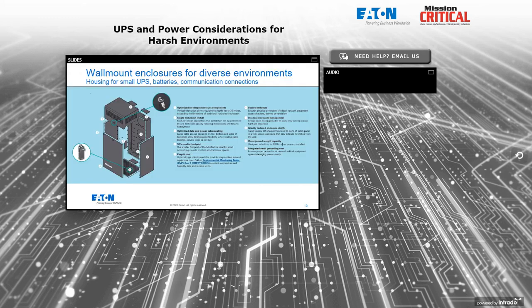One other thing that we see frequently for very small industrial UPSs is the need to wall mount them. If the UPS is, say, less than 2 or 3 kVA, typically I'm not going to want to set that on the floor in a harsh environment. I'm going to want to put it on the wall where I have better access to it, where I can keep it out of the way of water and corrosive liquids and things like that. But I need to be able to have it protected adequately, and I need to be able to secure it from prying fingers and button pushing folks who are not sure what they're doing there.